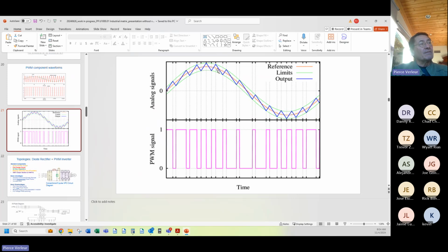So as you're climbing the sine wave, you widen your pulses. When you want to slow down and start going down again, you use narrower pulses. And then when you start to go up again, the pulses start to widen. Pulse width modulation technology is used to simulate the analog sine wave. We can only pulse width modulate on the traditional VFDs. We can't pulse amplitude modulate. It'd be nice to, because when we're trying to simulate the lower portion of the sine wave, we would like to use a half height or quarter height pulse, but you can't on a constant voltage drive. That's just the nature of it. It's what we've lived with since 1983, pulse width modulation.